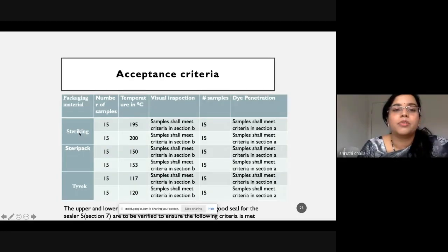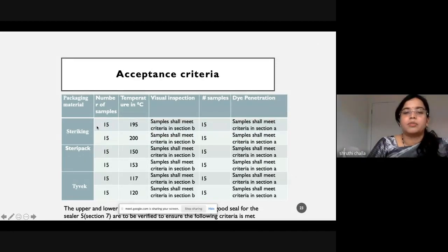So 15 samples of Steriking at 195 degrees, we do visual inspection. 15 samples, we do dye penetration. 15 samples at 200 degrees, we do visual inspection, and 15 samples for dye penetration. So altogether 15, 15, 15, 15 will be 60 samples. In that way, we have done for 3 different packaging types, checking both the lower temperature and the higher temperature. And we do those 2 tests, visual inspection and dye penetration. Depending upon the pass and fail, we'd set up the temperature routinely. If the sealing is good at 200 degrees, we'd operate the sealer at 200.